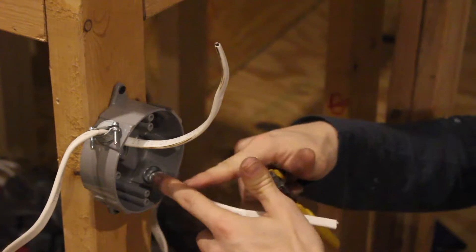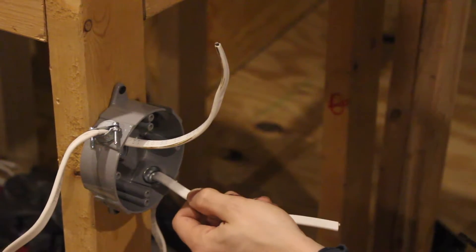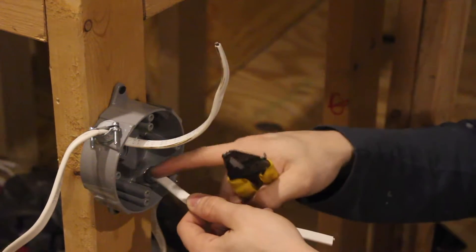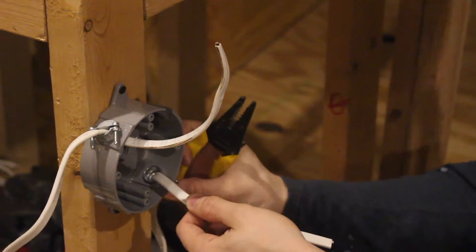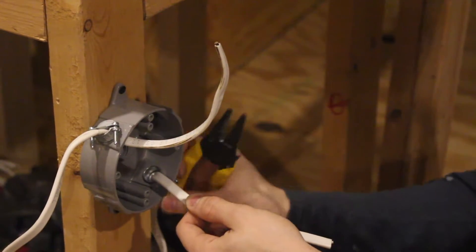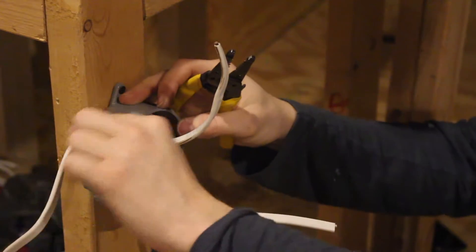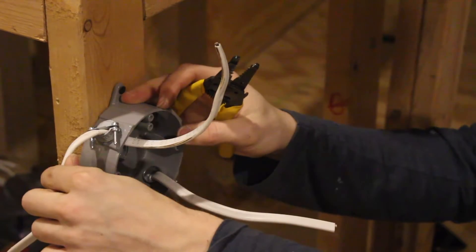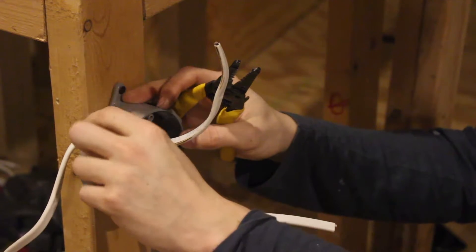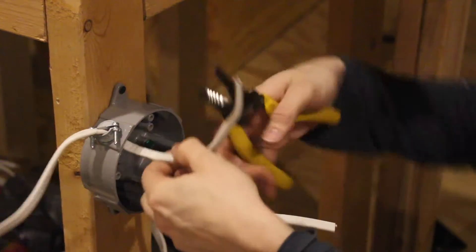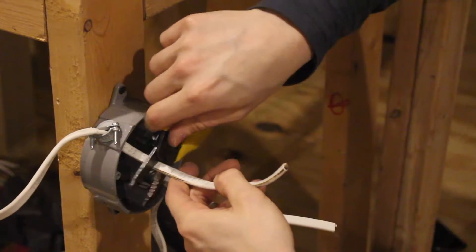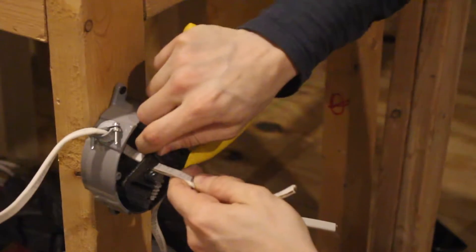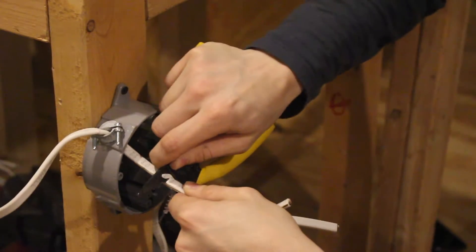You want to strip so that you've got a couple inches from your box so that the insulated part is still far from where it might be exposed. This is exposed wire - you don't want to strip it too close to here, so give it a couple inches and then you can strip the rest. Gives you a lot to work with.